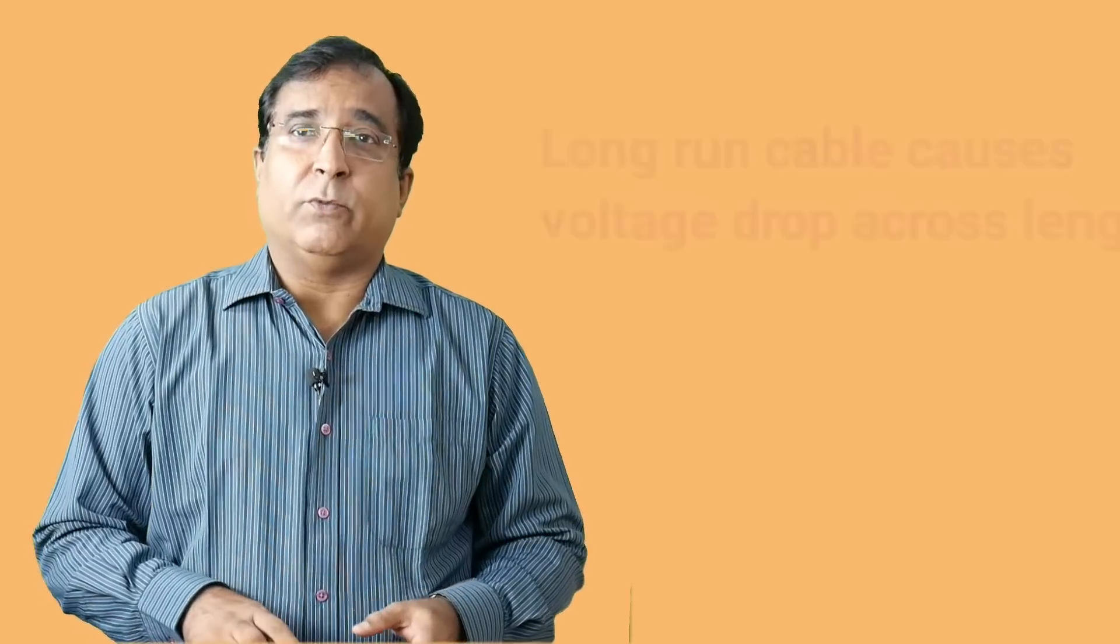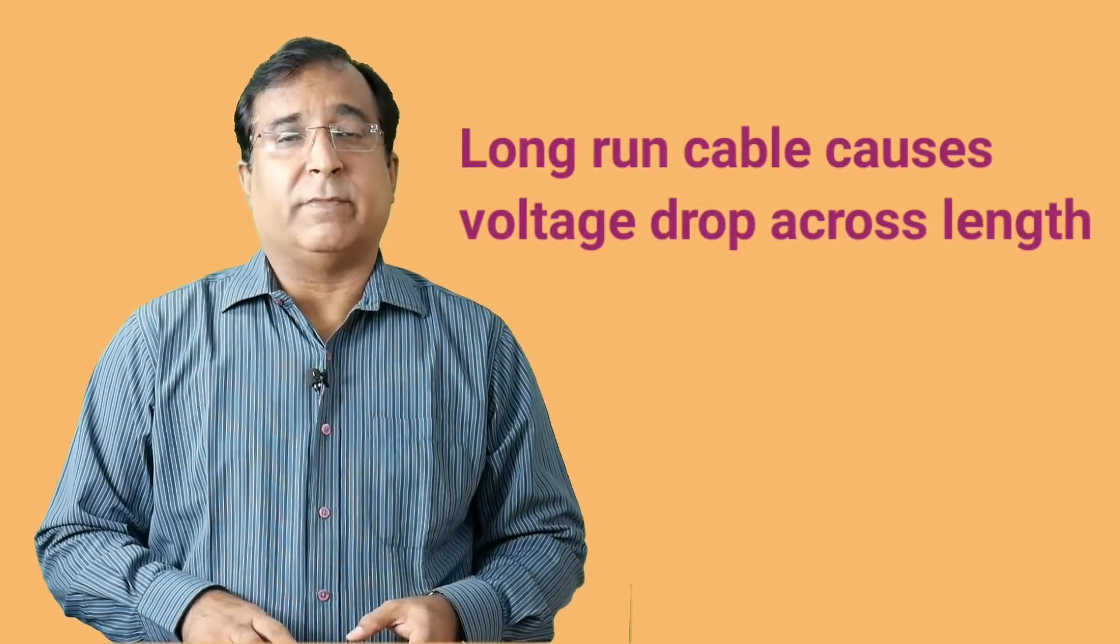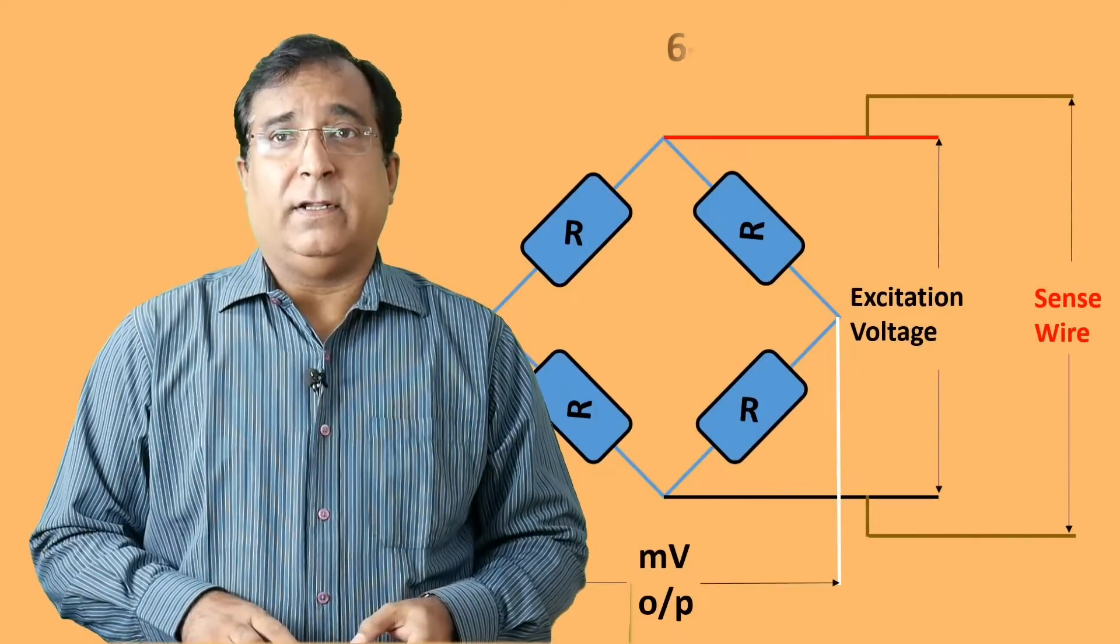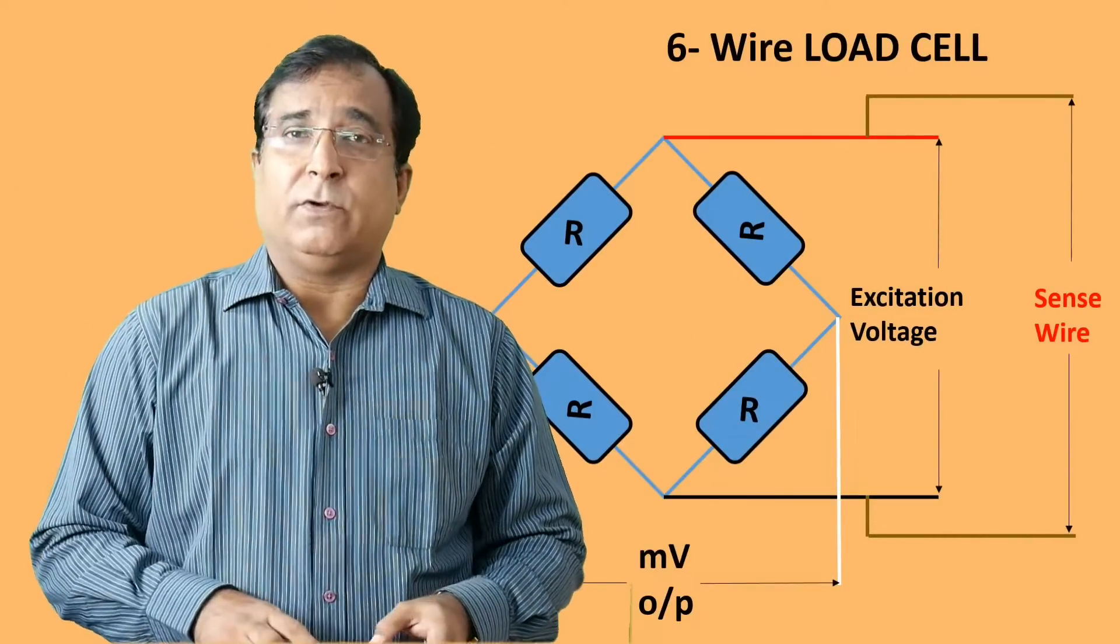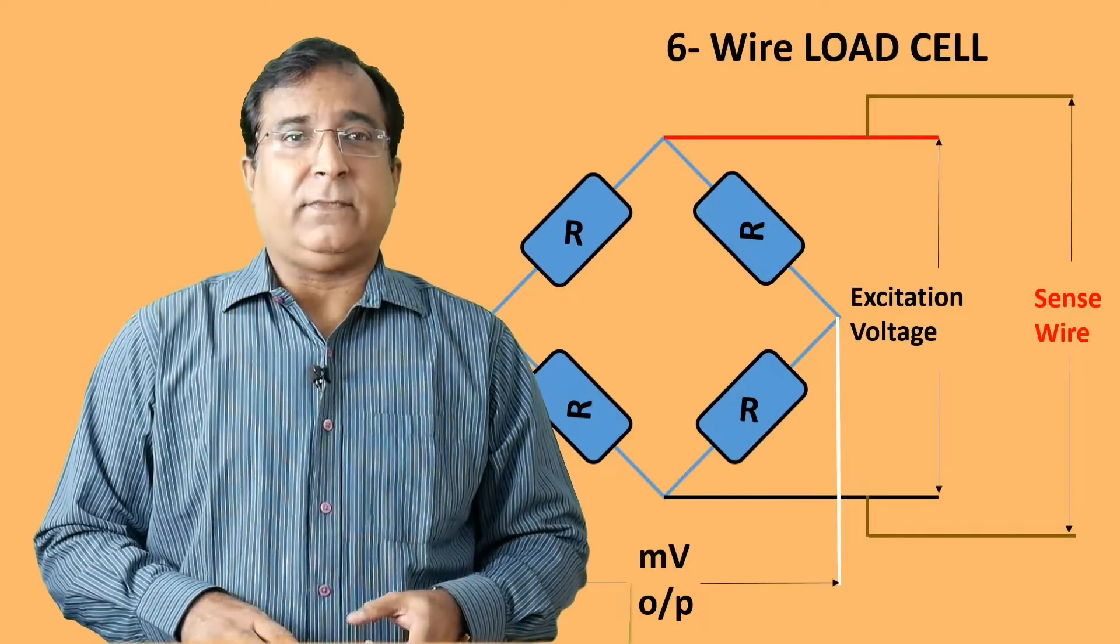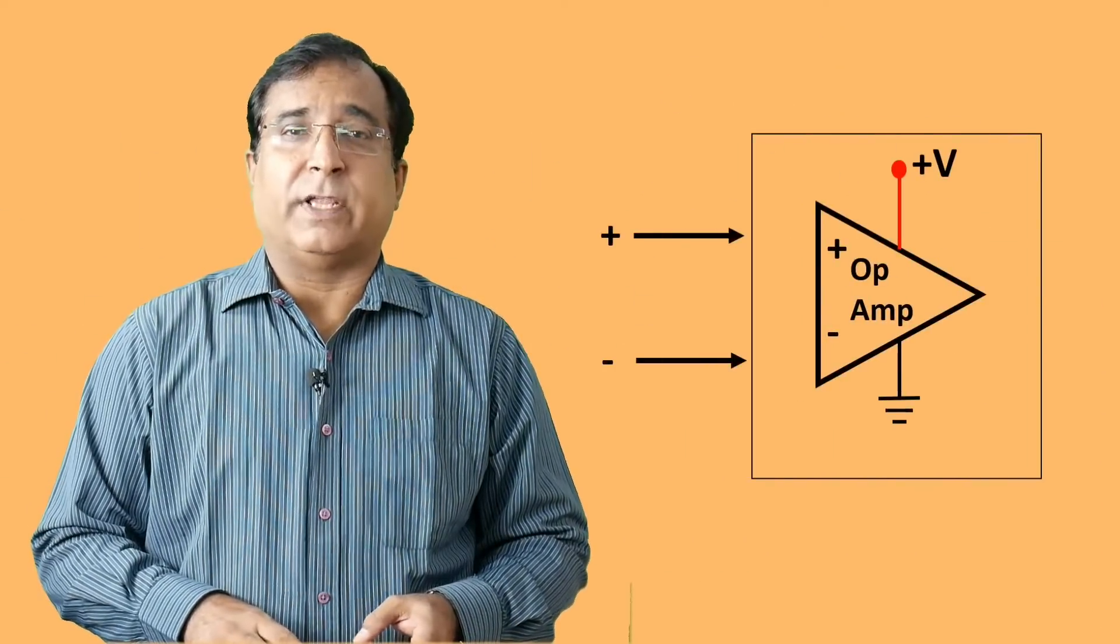But the cable length is supposed to be more due to remote measurement in the process plant. If a 4 wire load cell is used, then due to voltage drop the accuracy of weight will be compromised. That's why 6 wire load cell is used in remote measurement. In the same 4 wire load cell, 2 wires are extra added and which are connected parallel to the excitation supply wire. These are called sense wires. These 2 extra wires are meant for voltage drop compensation across cable length.